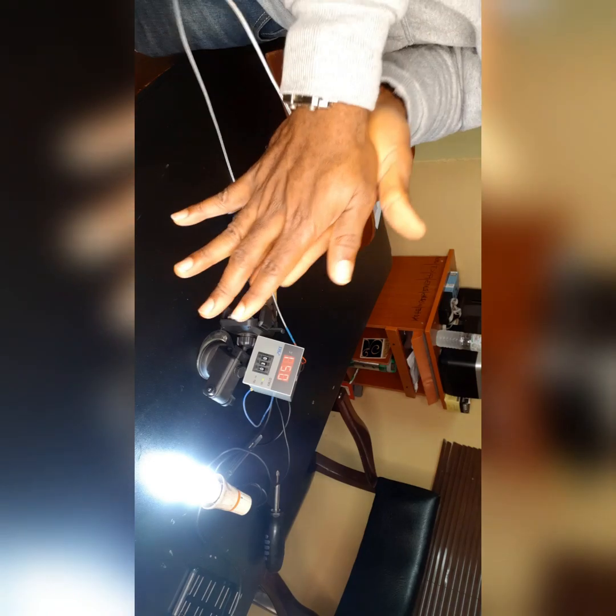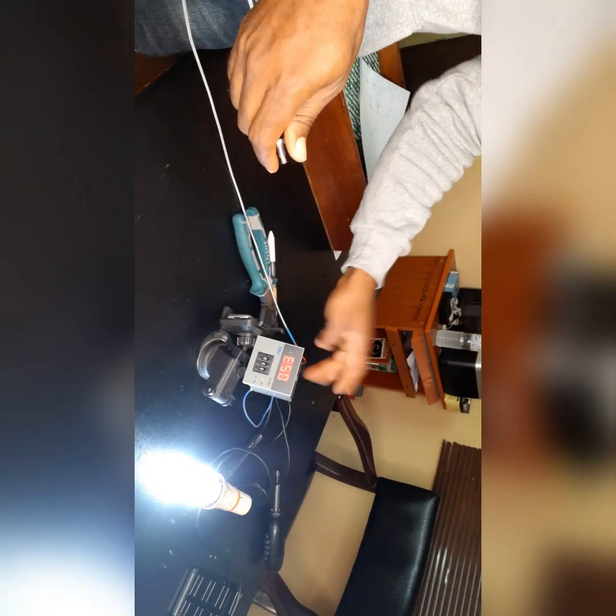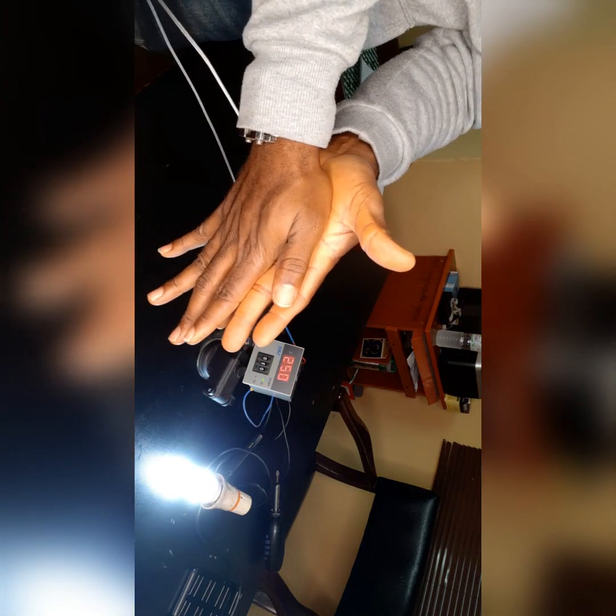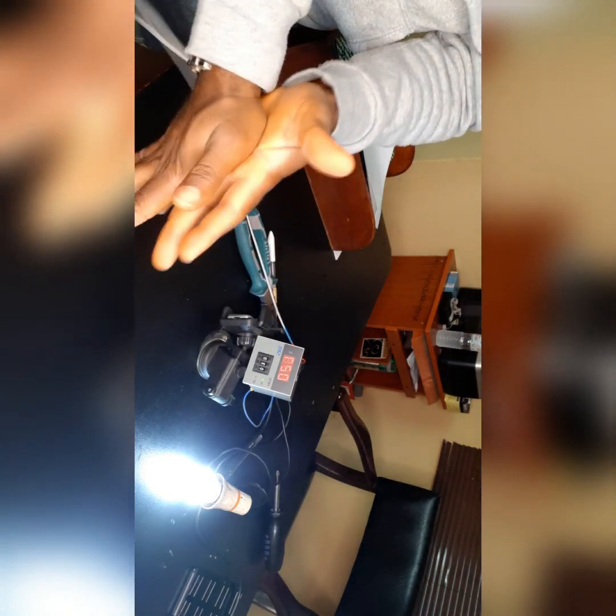So what I'm going to do is exert some heat here to make this probe heat up, and it will send it to this device. Then I will cool it with water. Once it gets to 30, it's going to trip off. Let's see how it goes. It's 24, now 25, 26, you can see it's going up, 27, 28, once it's 29, this is 30, the bulb has to trip off.